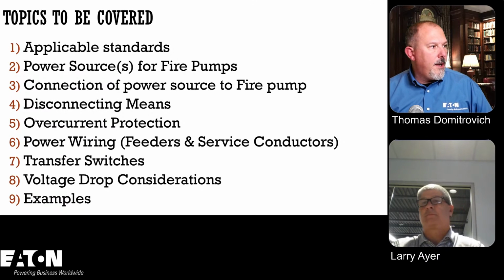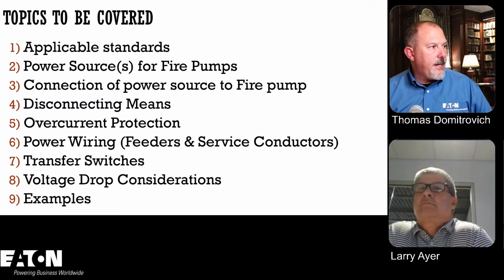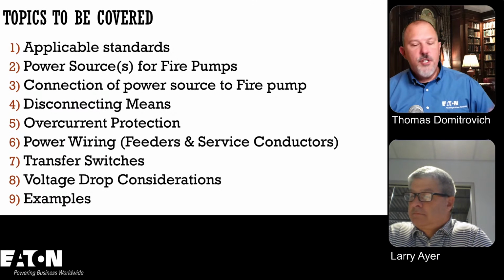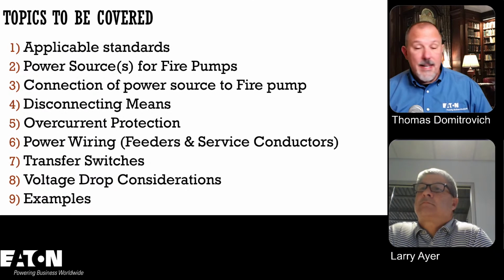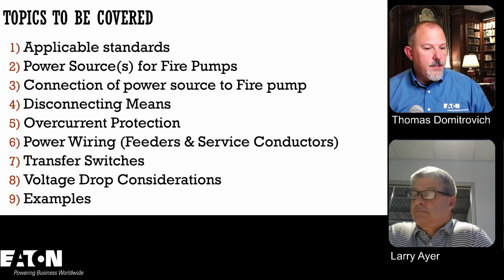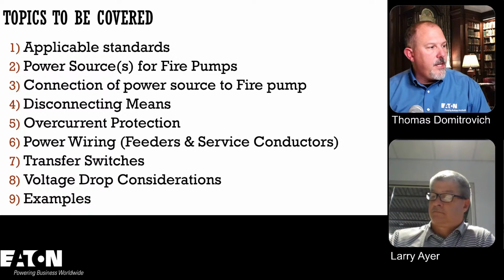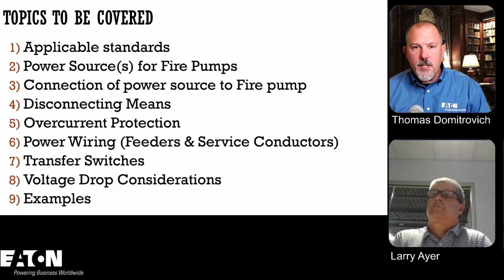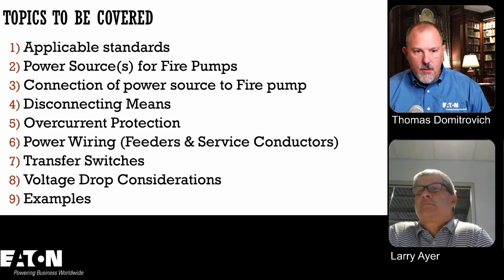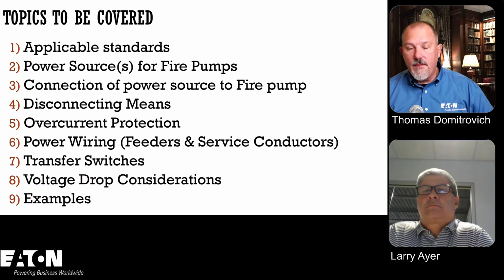Now, a type 1 is for indoor use to provide a degree of protection for personnel against access to hazardous parts. So I think what you're getting in the type 2 NEMA enclosures is protection against the ingress of solids and foreign objects. So they're probably protecting the electronics and whatnot more so than a type 1. But when you get into type 3, now you're getting into windblown dust and things of that nature, and rain and sleet and snow.